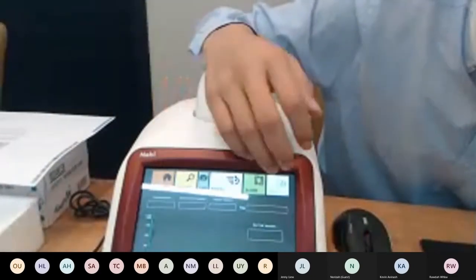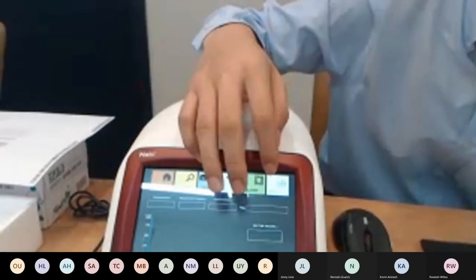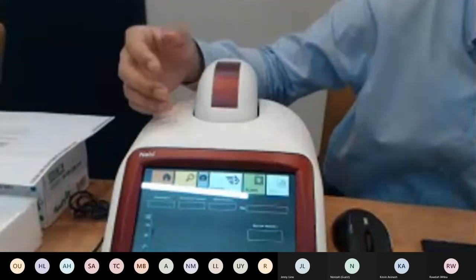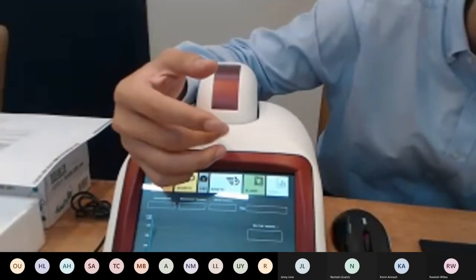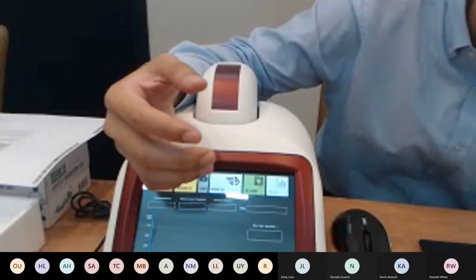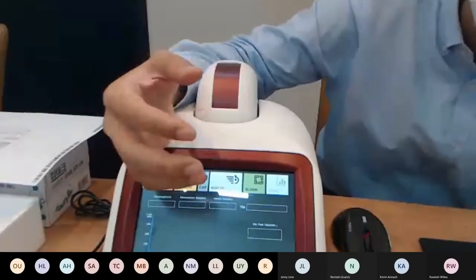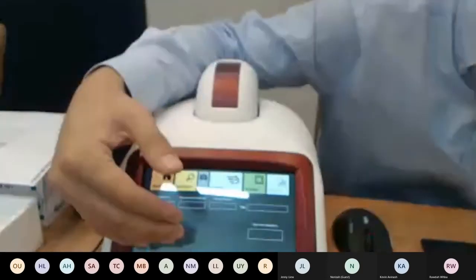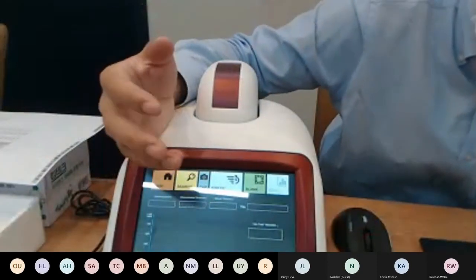We also have kinetic measurements where you can set the measurement time, interval, and wavelength, and the Nabi will continuously measure. For example, if you set the interval to one minute and the total measurement time to 60 minutes, it will measure every minute for 60 minutes — 60 times total — and you'll see a graph of the concentration change over time.